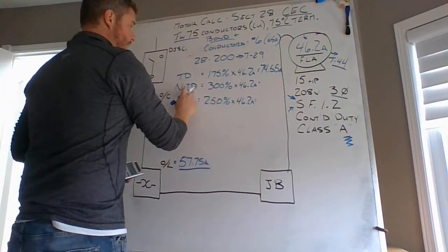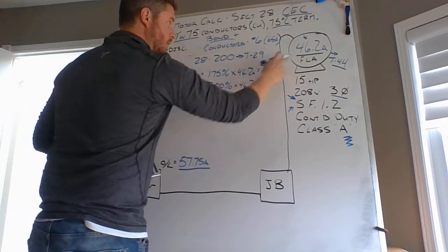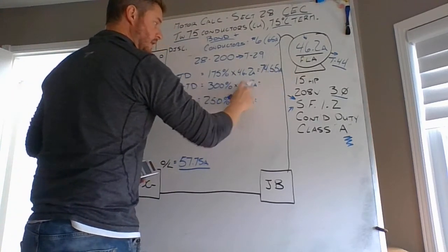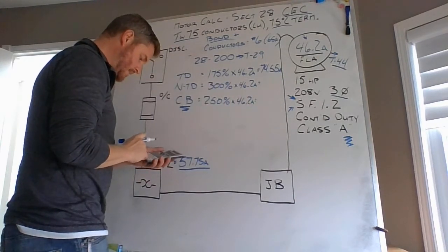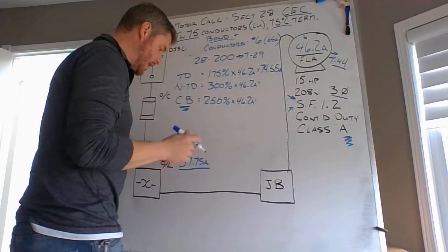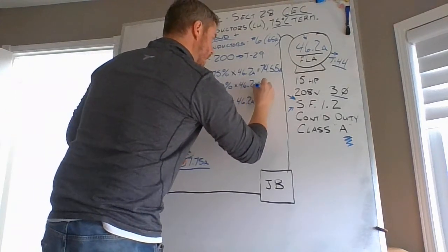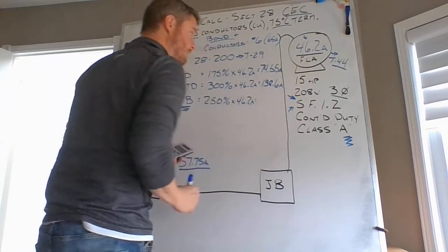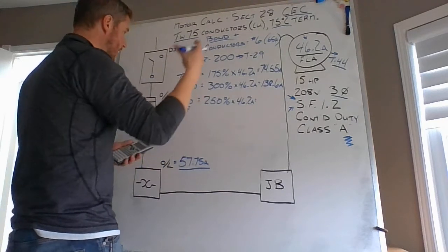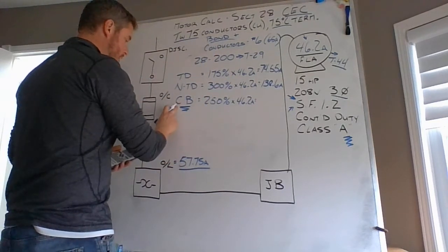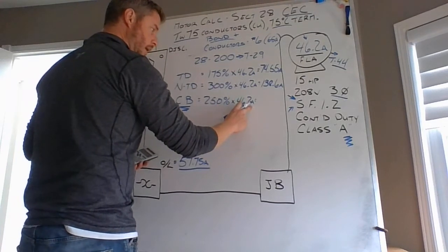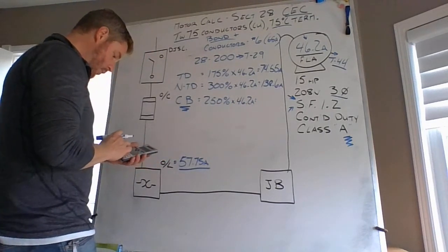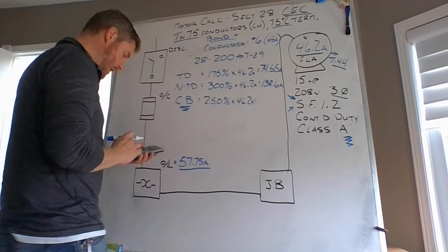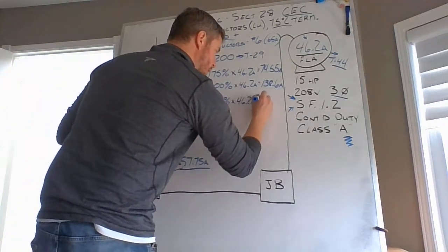A non-time delay fuse is rated at 300% of the full load current rating of the motor, which is 46.2 amps. So 46.2 times 3, or 300%, leaves me up to 138.6 amps as a maximum calculated overcurrent device. A circuit breaker is 250% of my full load current rating, being 46.2. 46.2 times 2.5 gives me 115.5 amps.